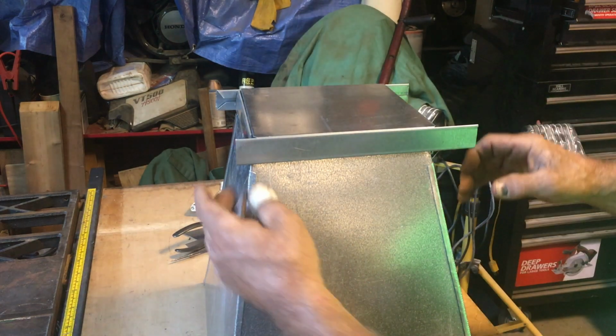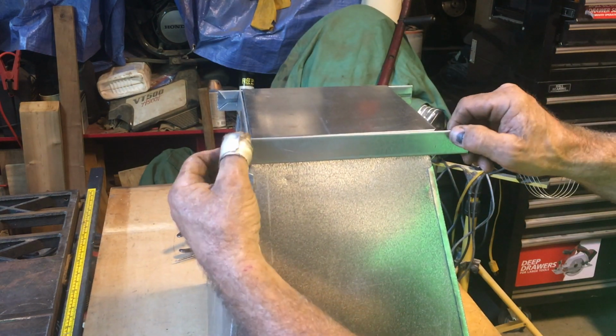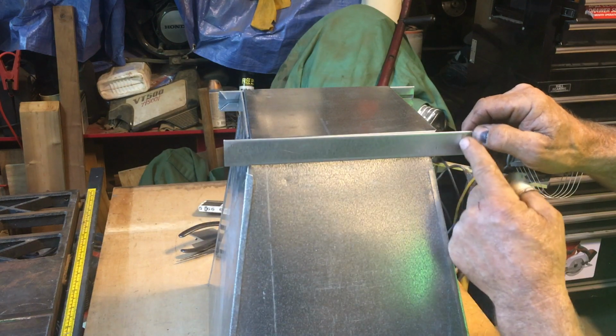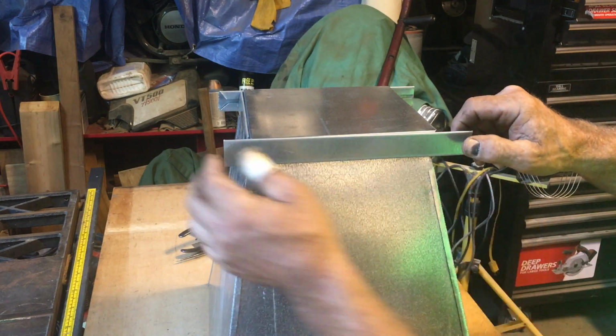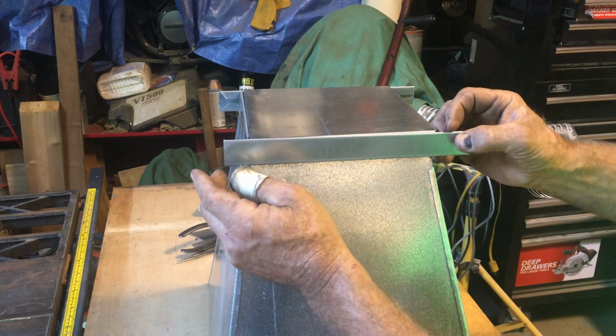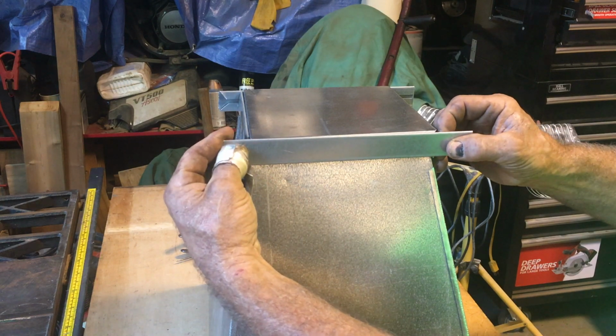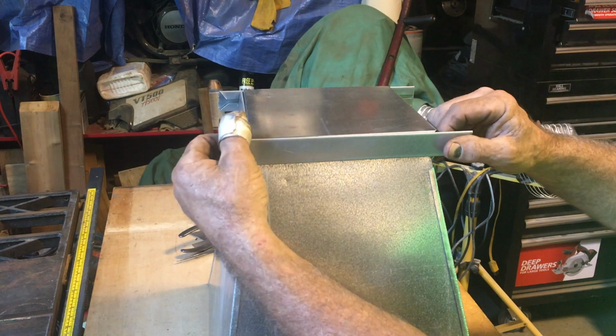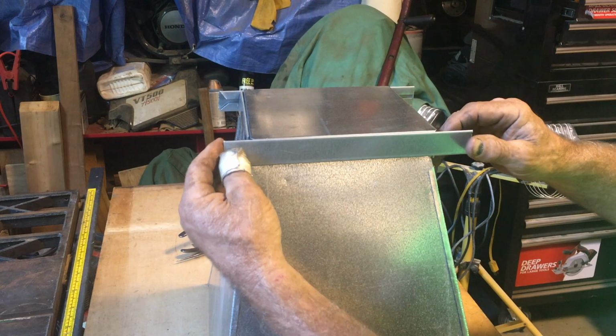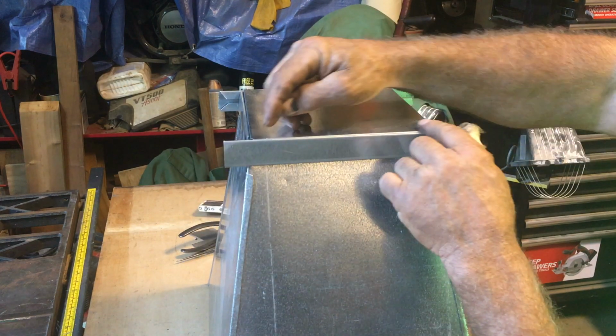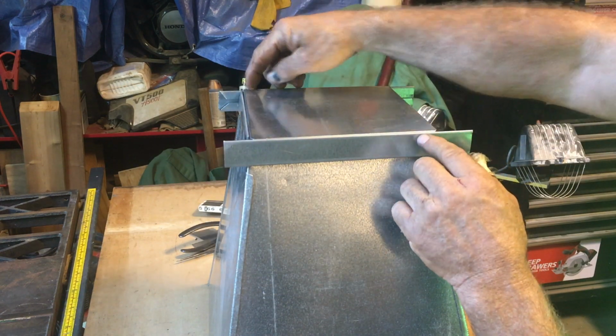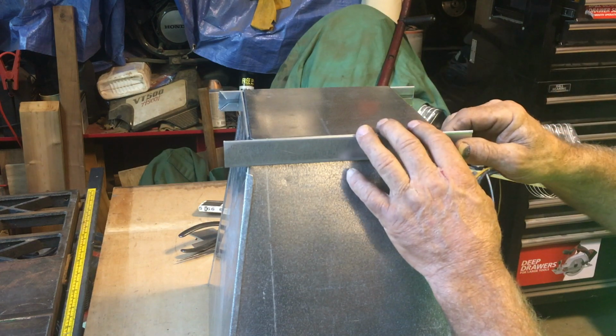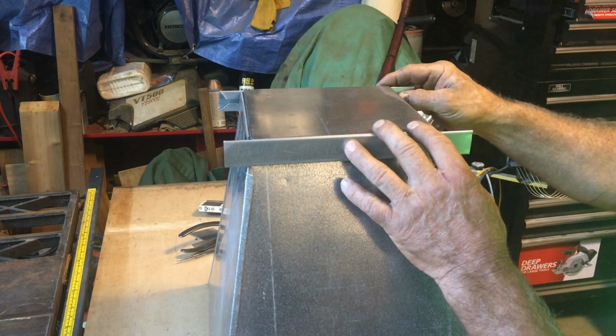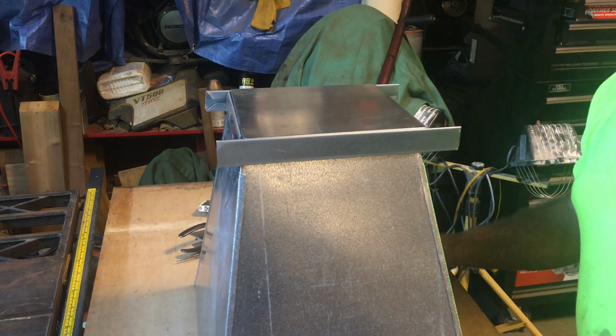When I get done, ready to install it, I'll trim this off perfectly about 1 inch beyond, put some little angles on the end to trim it up, bend it with a pair of folders to get a perfect 90-degree bend, and latch it down nice and tight. Do that on all 4 edges, and there won't be anything except a very small pinhole at the 4 corners that'll leak just a little bit of air. But that's pretty much it in a nutshell.